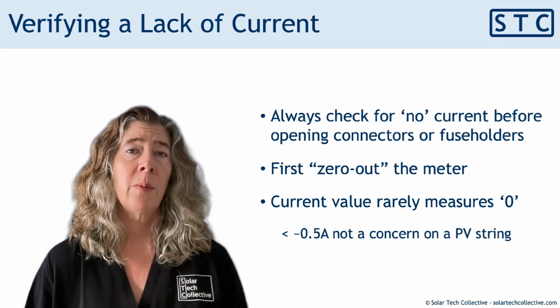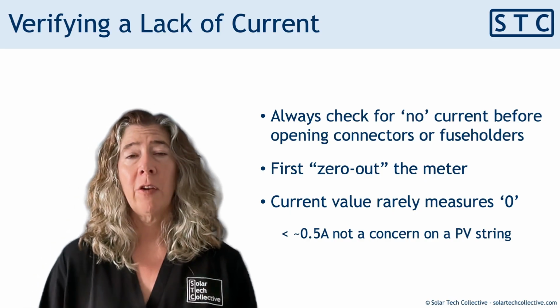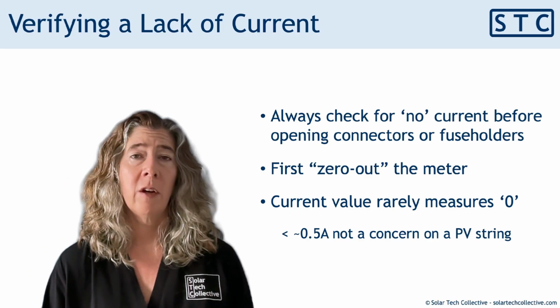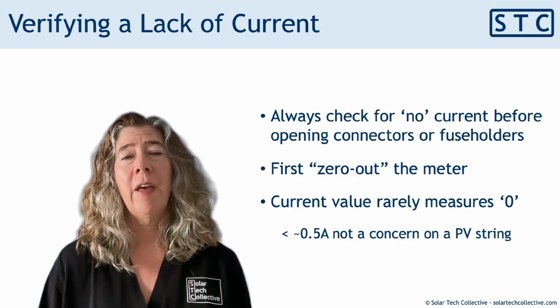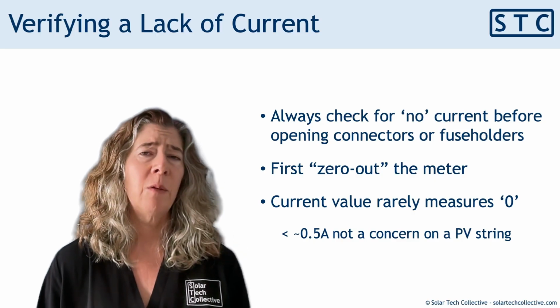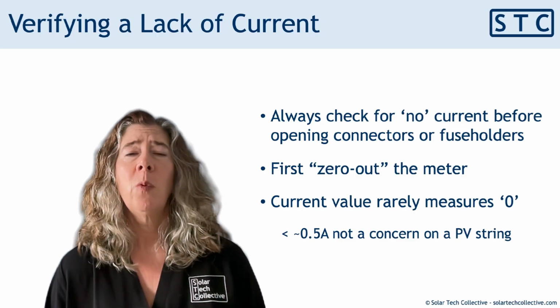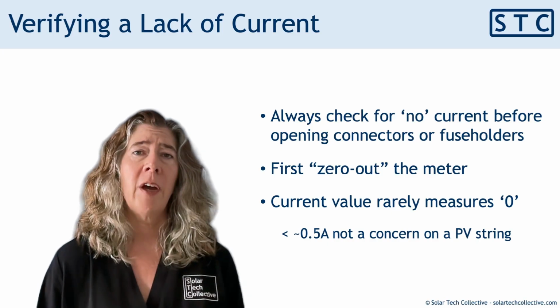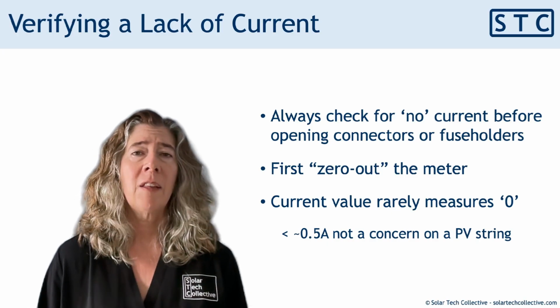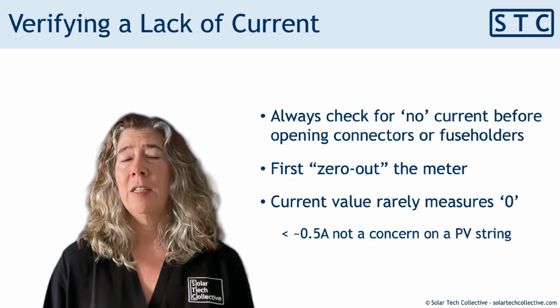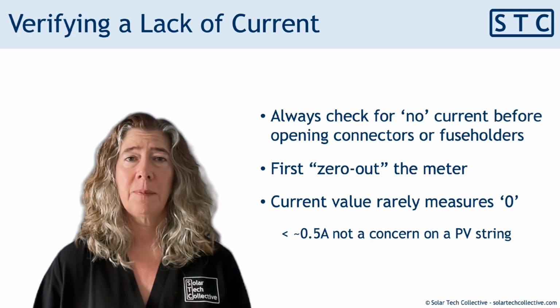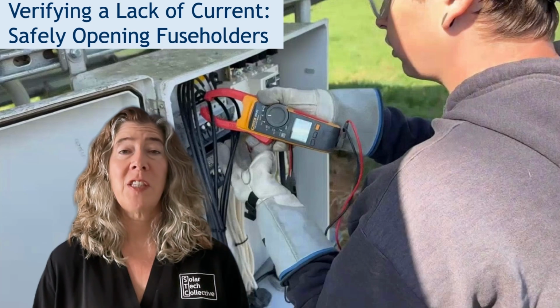First, you need to zero out your meter. Make sure that you're getting an accurate reading from your meter. You should be aware that the current value is unlikely to read as actually zero. We'll usually see some fluctuating low current values when we check PV circuits. Less than about a half an amp is nothing to be worried about. Okay, let's head out into the field and watch this in action.